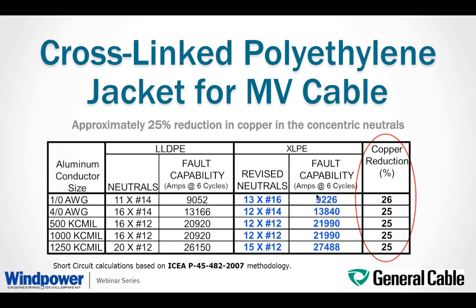On the next slides, I'm going through various sizes of typical wind farm cable construction, showing more visually the impact on the reduction in copper content in the concentric neutral. Here you can see that it will definitely have a much bigger impact on the larger sizes. But even with the smaller conductor sizes, which normally have the larger neutral in terms of conductivity relative to the phase, you will still have some significant savings, even just in copper content and upfront cost, by going with the reduced neutral design with the XLPE jacket. In general, you can achieve approximately 25% reduction in copper in the concentric neutral.